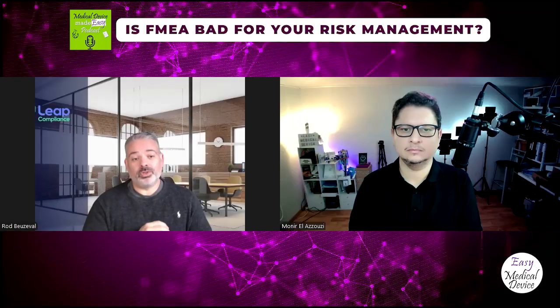It's not a problem per se, but you just need to understand that FMEA doesn't meet all of the requirements of the standard. And so that is where the title "FMEA is bad" is coming from, because if you just use FMEA from a template that you found, then you will not be meeting the requirements of the standard.